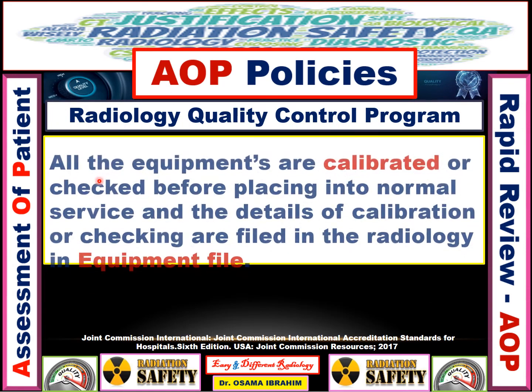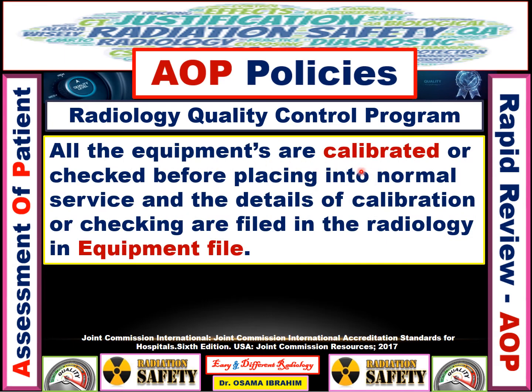In the radiology quality control program, all equipment is calibrated or checked before being placed into normal service, and the details of the calibration or checking are filed in the radiology equipment file. This file is very important, saving all dates and details of machines that should be calibrated before starting clinical use.